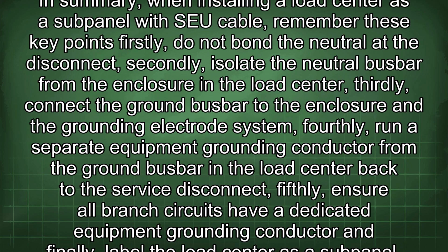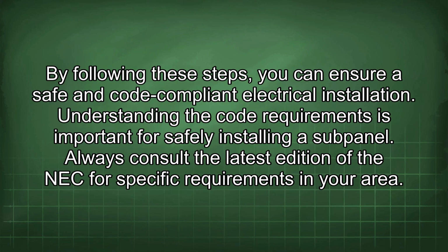In summary, when installing a load center as a subpanel with SEU cable, remember these key points. Firstly, do not bond the neutral at the disconnect. Secondly, isolate the neutral busbar from the enclosure in the load center. Thirdly, connect the ground busbar to the enclosure and the grounding electrode system. Fourthly, run a separate equipment grounding conductor from the ground busbar in the load center back to the service disconnect. Fifthly, ensure all branch circuits have a dedicated equipment grounding conductor. And finally, label the load center as a subpanel. By following these steps, you can ensure a safe and code-compliant electrical installation. Understanding the code requirements is important for safely installing a subpanel. Always consult the latest edition of the NEC for specific requirements in your area.